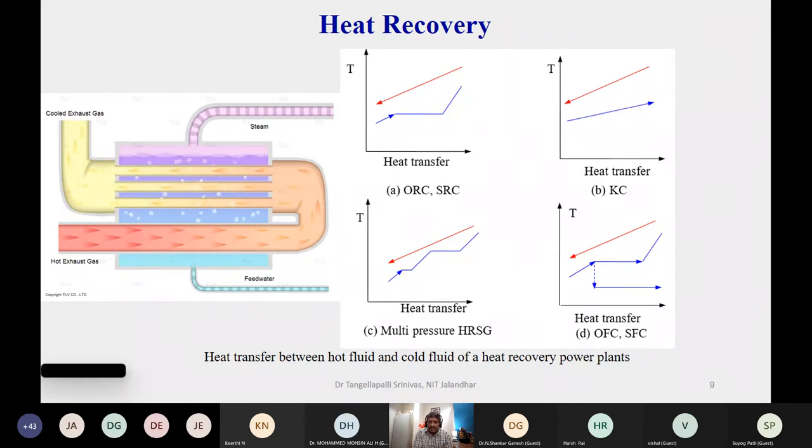Once you are expanding the liquid at the exit of the expansion, it's not like turbine expansion. It's a restricted process, same like throttling. It's flashing. That's why it is called flashing. The liquid is flashed. What are we expecting at the exit? It will be a mixture of liquid and vapor. Yes, exactly. It's a mixture of liquid and vapor. So you are generating some additional amount of vapor that can be supplied to the turbine.